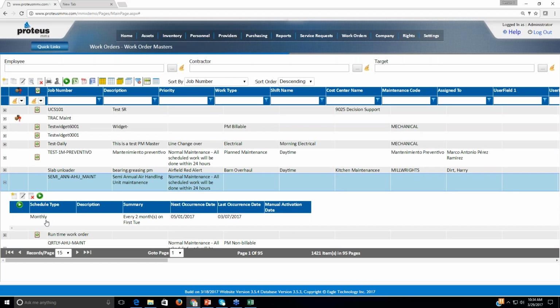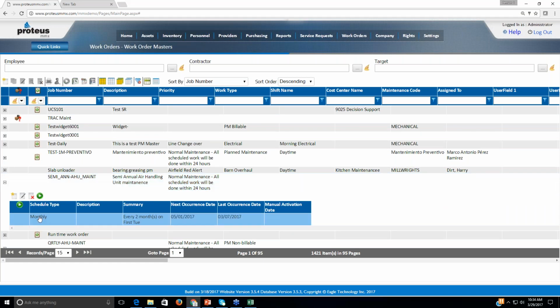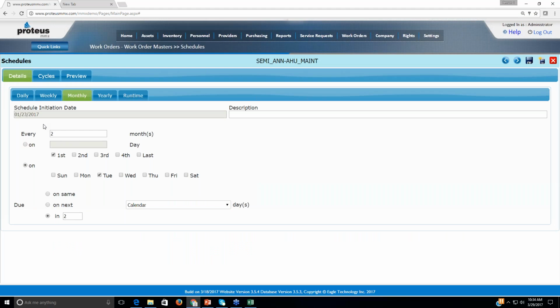Right now the task says semi-annual, but it's scheduled for every 2 months on the first Tuesday - that might be a mistake, or it could have been corrected with the name left different. Let's go in and make this properly semi-annual. Since there's no work order open on it, I'm able to bring up the schedule. It should be every 6 months to be semi-annual, and instead of the first Tuesday, I'd like it on the second Wednesday of every 6 months. I'll also give the contractor 3 days to get the work done.